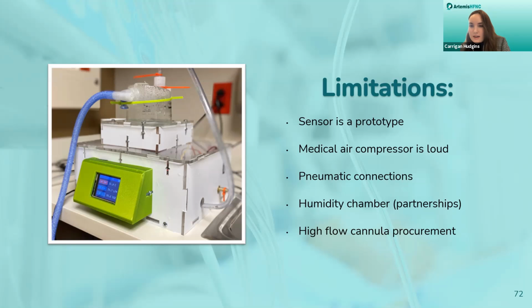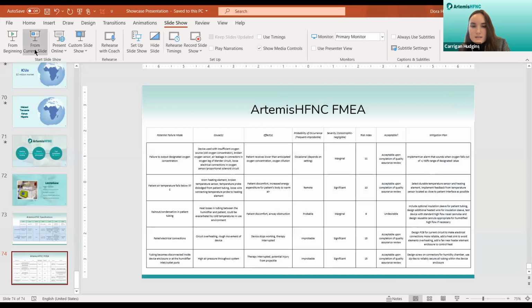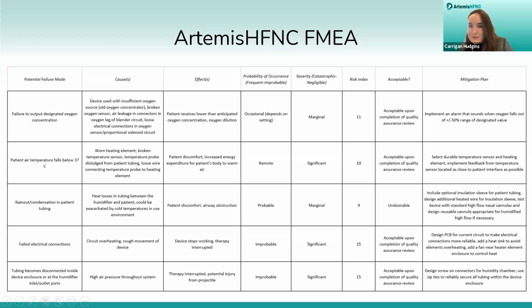Yeah, Dora, would you mind going to the FMEA slide? Perfect. This is very small text, kind of hard to read, but we have fleshed out a pretty thorough failure analysis of the device. One of the failures is what you mentioned, condensation in our tubing, which we do experience, especially in settings where it's colder outside than in the heated air. To remedy that, we have included an optional cover for the tubing that leads to the patient, which helps minimize the effects of the cooling as the air travels to the patient interface.